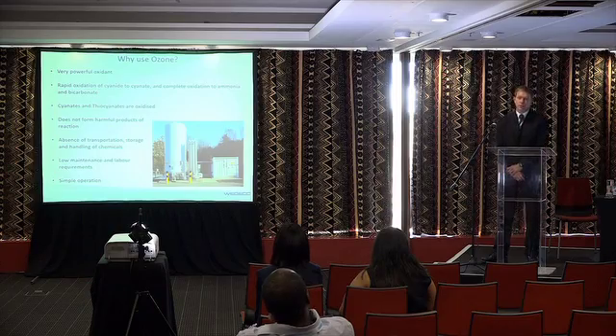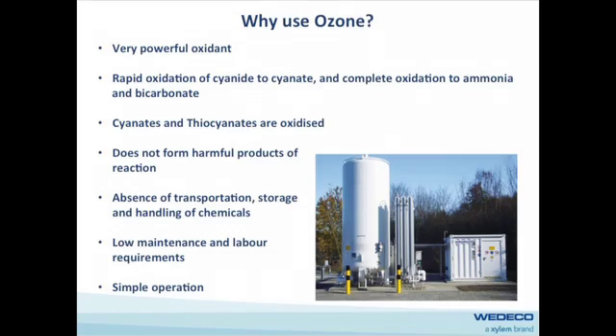It's also a purely on-site technology. Because you cannot transport or store ozone, you have to generate it on-site. You can either use LOX — a liquid oxygen tank — or an oxygen generation system to generate oxygen and pass it through your ozone generator. Your only on-site requirements are power and cooling water. It's very low maintenance with minimal labor, and we can go from zero to 100% capacity in less than about a minute and a half for larger generators, with a turndown ratio of 100% down to about 10% — so very flexible on sizing and control.